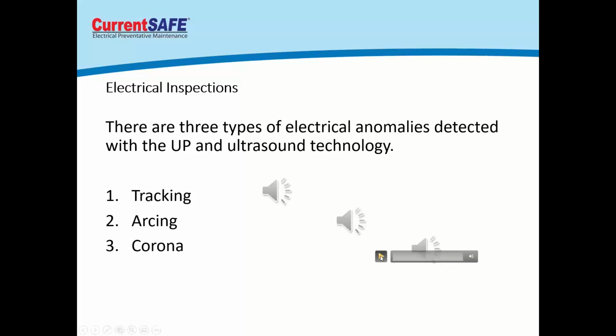Next, in the medium voltage world, like I said, is corona, and we can hear it. Some of you may be familiar with hearing this if you work and live around high voltage lines, overhead lines. Sometimes you can hear corona, especially when it's really foggy and cool in the morning. You can hear this on rainy days as well if the electrical distribution and transmission systems are close enough to where you can listen underneath. To me, this sounds more like an AM radio static, but what's happening is the ions are releasing particles as the air is being stressed by the voltage. So the voltage really stresses the air around it, and it is jumping off and smashing into other particles in the air, and they're releasing ions, and that's what we're hearing, the turbulence there with the corona.